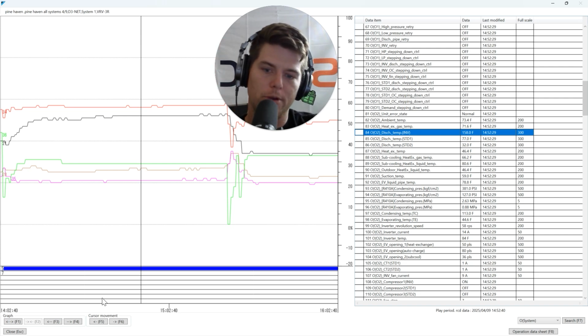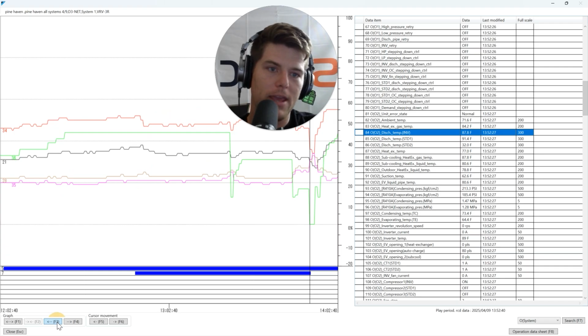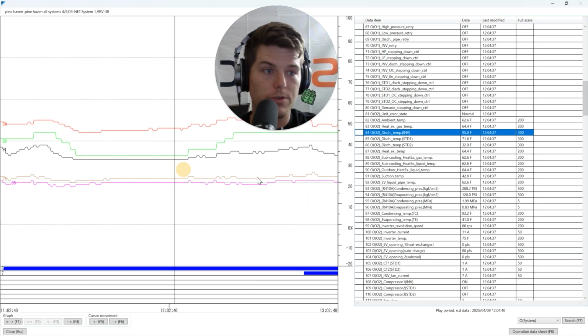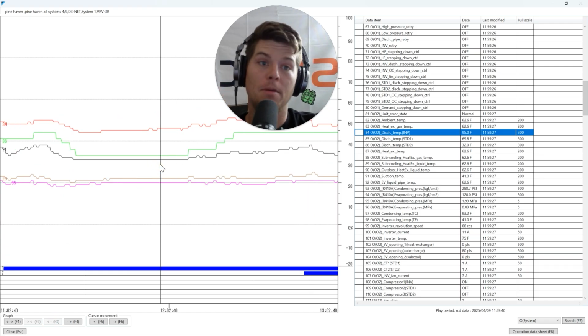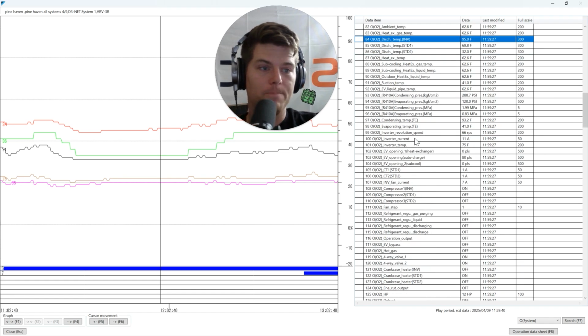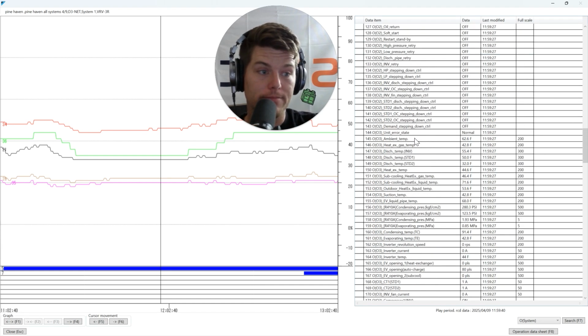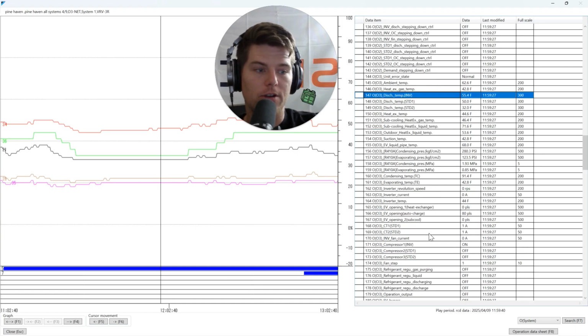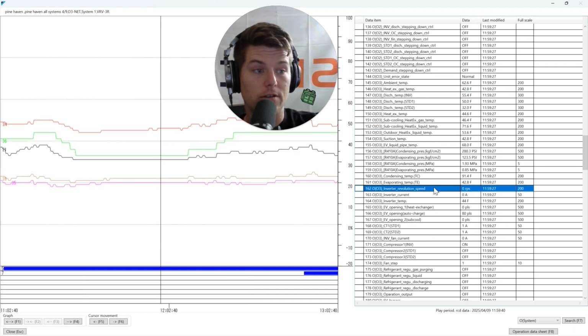So we know we have low discharge superheat, we have low suction superheat, we've got all the makings for liquid compression, and it shows. Okay. And I'm going to jump to the solution so I don't make this a 40-minute video. What about O3? What does the outdoor module number 3 look like? And so what I do here is I want to say, okay, this unit, 0 RPS.